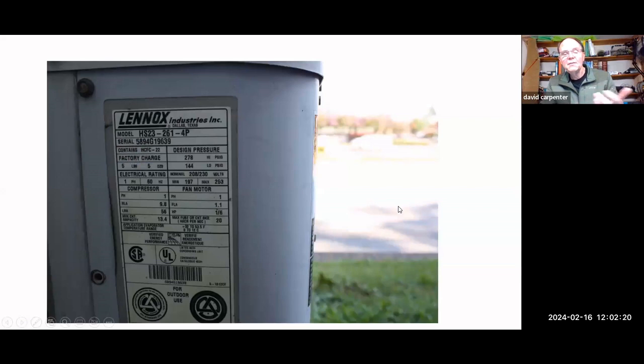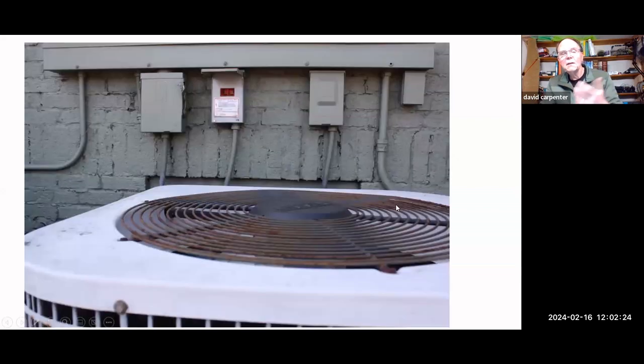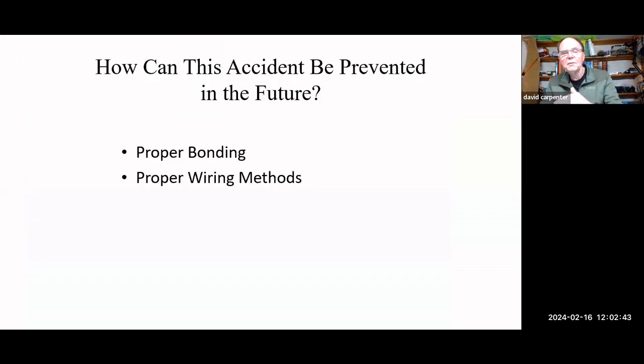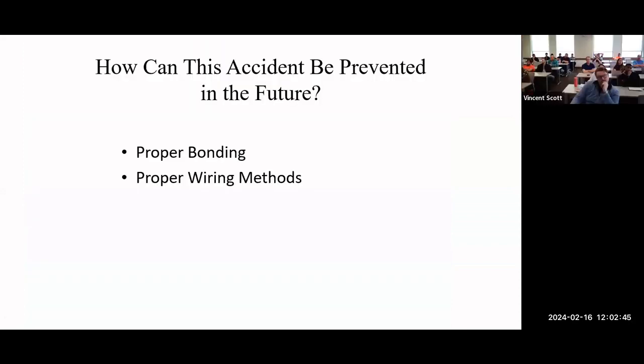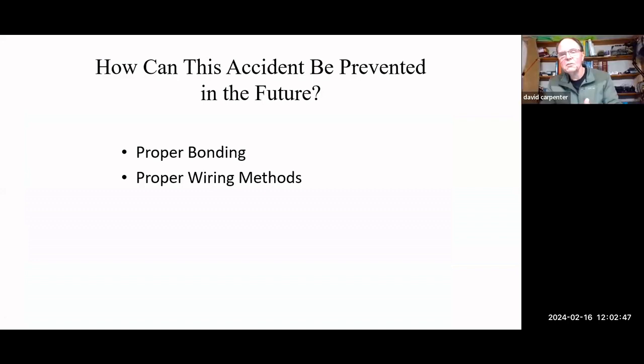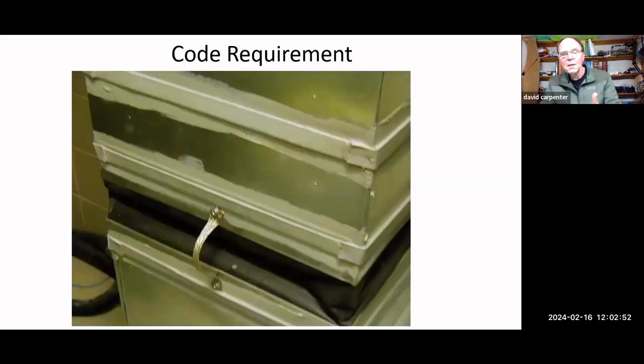We looked at the HVAC unit to make sure there wasn't a problem there, and we checked the overcurrent protection. So let me tell you what actually happened. It had nothing to do with the overcurrent protection itself, other than it wasn't installed correctly. This would never have happened had the cable been in the right place and properly protected. What we found was poor wiring methods, which I just described concerning the cable, but also poor bonding.